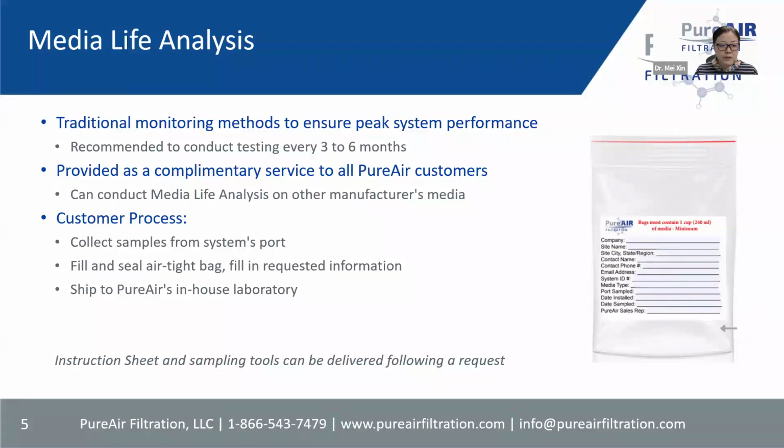The process for the customer is to collect the samples from the system port, fill and seal the sample into airtight bags, fill in the request information, and ship the sample to our new location. This is provided as a complimentary service to all our PureAir customers. We also have the capability to conduct media analysis on other manufacturers' media.